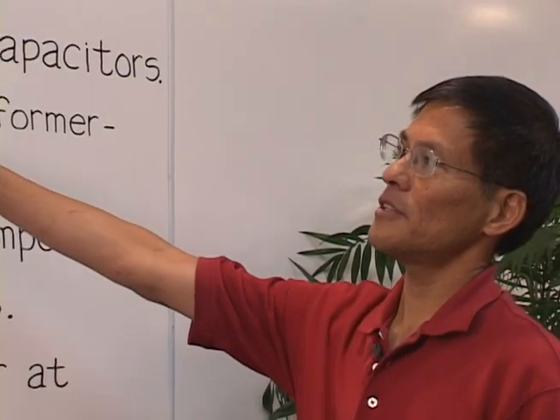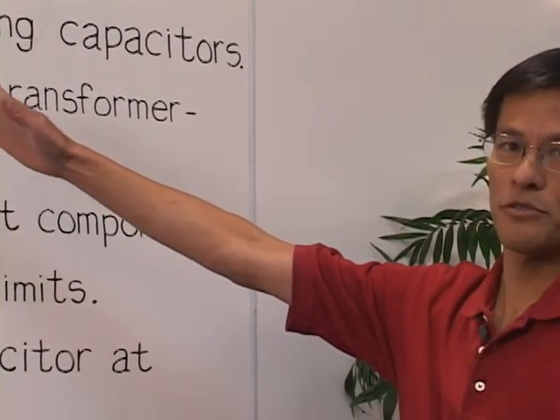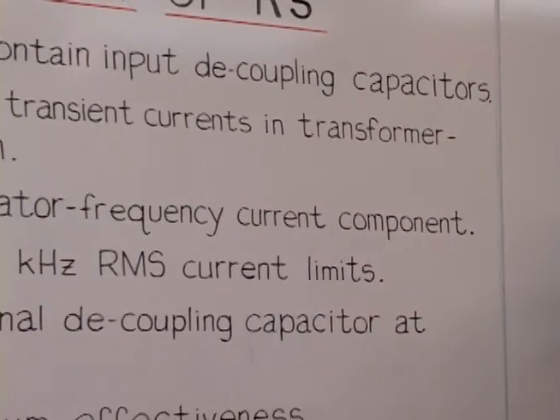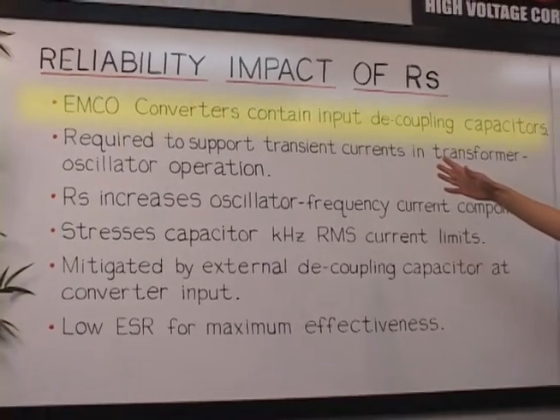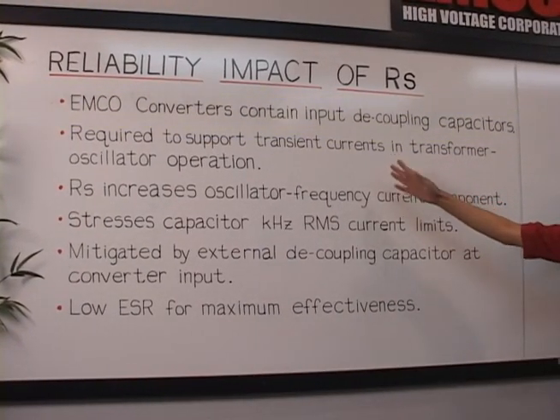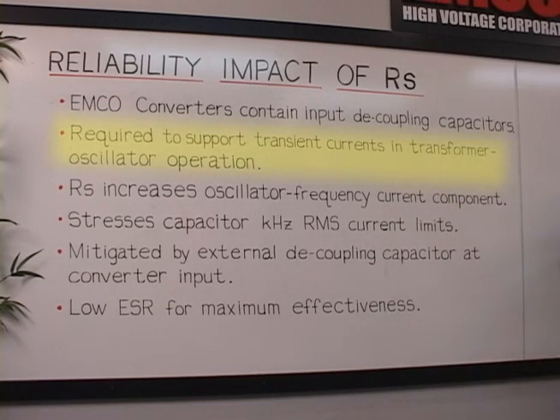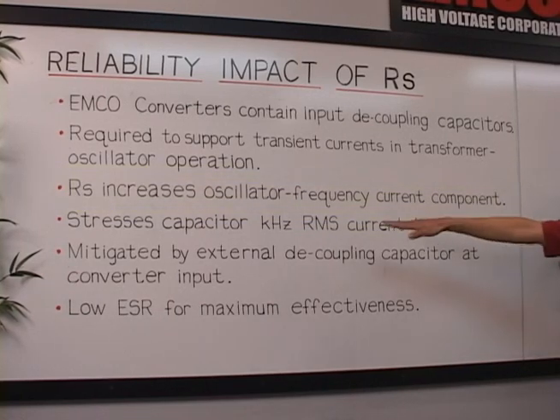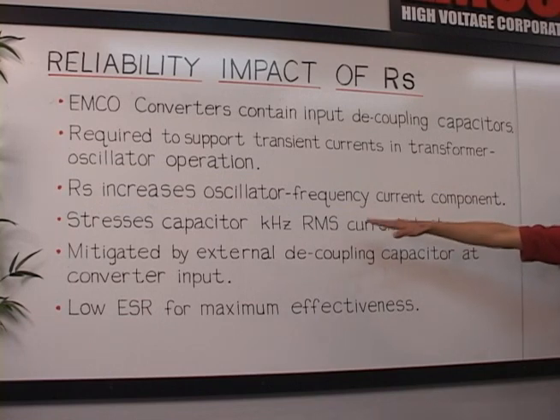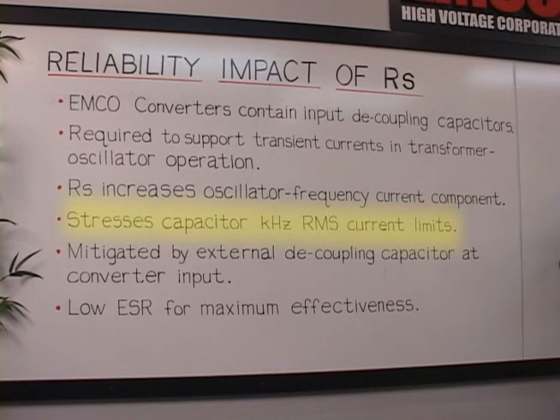In addition to efficiency, there's a reliability impact of source resistance on the operation of the converter. EMCO converters contain input decoupling capacitors, as we saw earlier in the block diagram. These capacitors are required to support transient currents that are inherent in the operation of the oscillator-transformer combination. The source resistance increases the oscillator frequency component of that current, which leads to stress on the input capacitor because the input capacitor has kilohertz range RMS current limits.